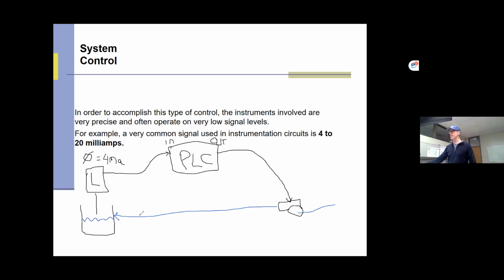And when this tank gets to a certain level, all of a sudden now I'm not reading 4 anymore. I might be reading 15 milliamps now that the tank's getting full. And that's what I've programmed my PLC to say: at 15 milliamps now, turn this pump off. And now that will send a signal to that pump. It shuts off, shuts the water off until it can go again.